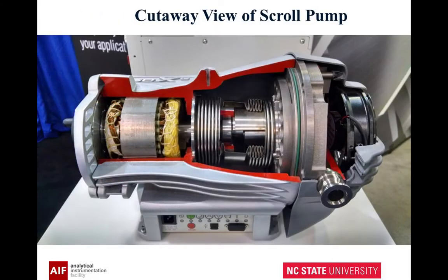Question: how much concentration of flammable material is needed to blow up a pump? If you're pumping any flammable material, I really ask you to consult with a few people to see what kind of volume you have. If it's a very small volume, that's probably not going to be a problem. But if you've got a process where you're continuing to flow a flammable material, that could be a very significant problem. Before starting to pump something like that, please check with safety, and also consider having a filter which would react with the flammable material before it hits the pump.